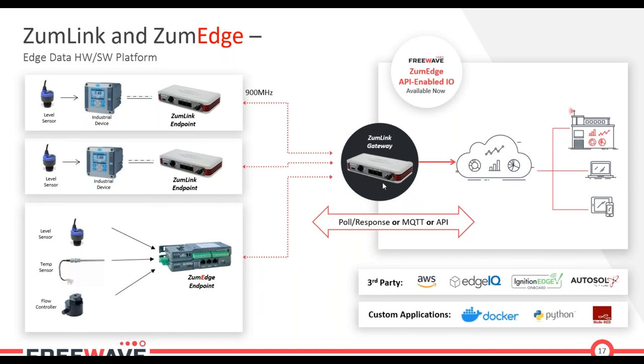Over the air, we're talking 900 megahertz unlicensed, so 902 to 928. As I mentioned earlier, it could be 500 feet. It could be up to 10, 15 miles sometimes in an open air environment. The types of obstacles that 900 meg can penetrate really depend upon what the material is. Sometimes gentle rolling hills will work okay. We have some links that are through buildings and manufacturing facilities. It just really depends on what the material is. Probably the worst thing you can put is a filled concrete block. Those older buildings that are poured concrete, sometimes those can be difficult. But I'm usually surprised with 900 megahertz.